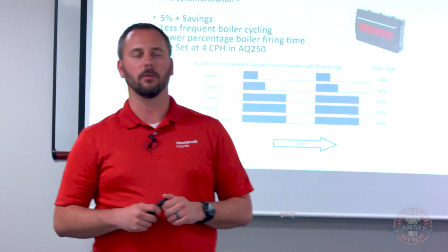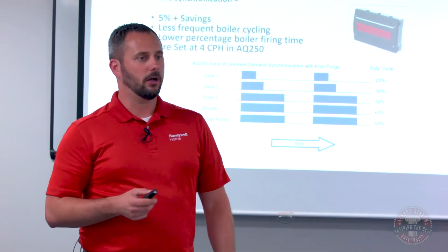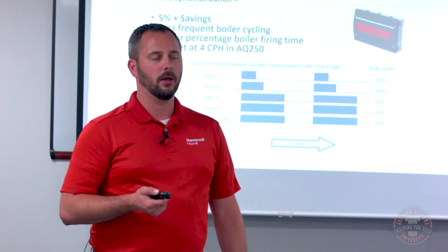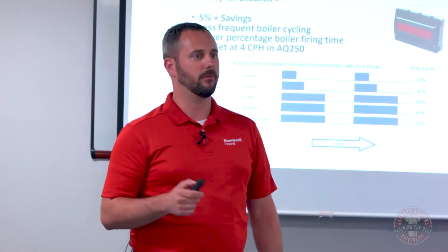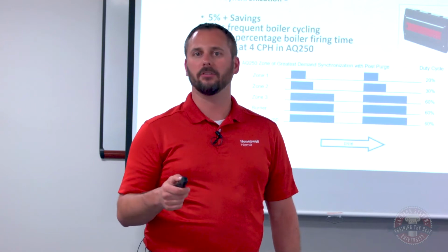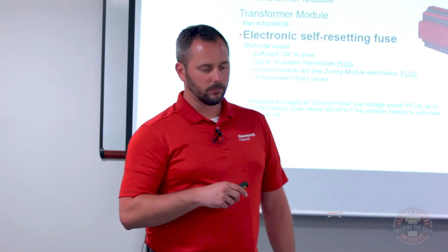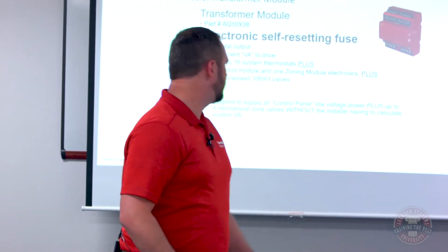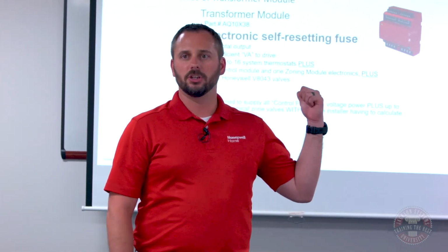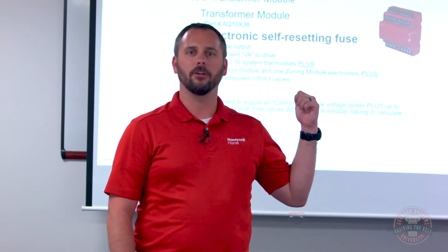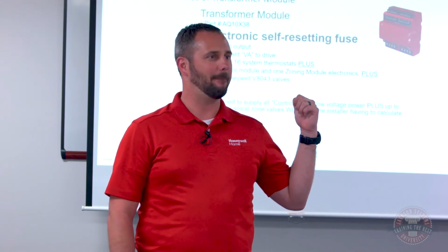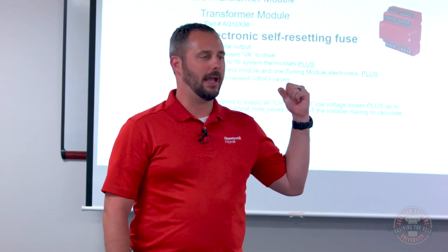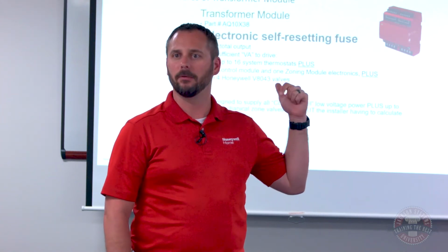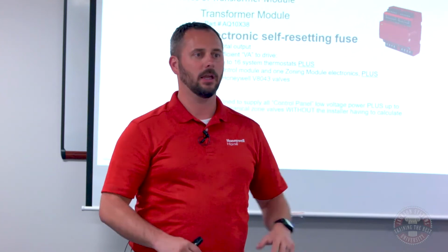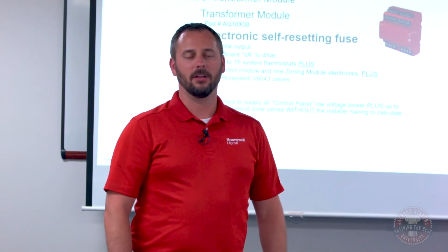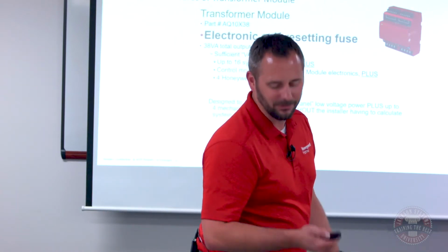But it will basically produce less cycling on the boiler. It's not dramatic on the energy efficiency savings, it's roughly 5%. But what it does is it prohibits some of the boiler cycling, so incredibly less wear and tear on the equipment. The other thing that's neat with this, and I wish I had one that was live fire, you can literally jumper between R and C. So anybody that's done that on a transformer, what happens? It goes pop. This one, it's auto resetting. I have no idea how the engineers did this, but you can put a jumper between R and C. You can watch sparks fly, and it'll just keep going. So that's fun to show. I should have brought one of those and plugged it in.